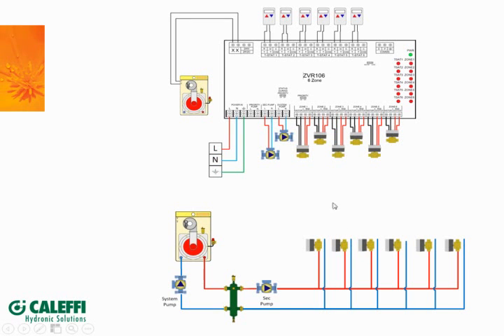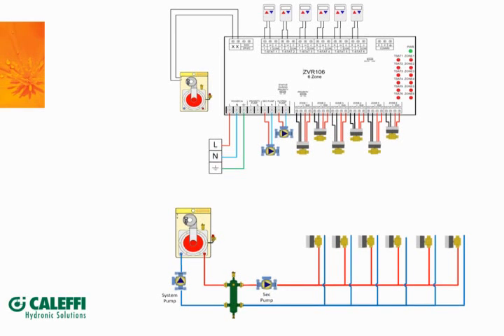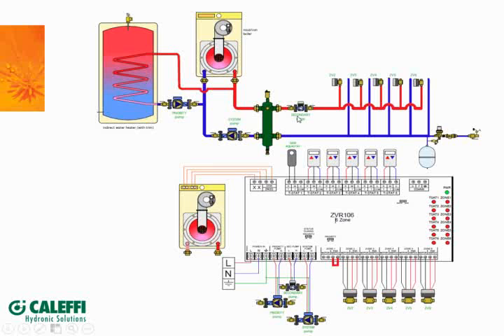booklet color. So here's another, this is another basic one. Kind of touched on this before, but if you had 6 zone valves, a system pump and a secondary pump, the control could control all of those items in that particular system. And getting a little bit fancier here, we have 5 heating zones, our secondary pump, a system pump, and a priority pump. And of course, many boilers can't control that, and that's fine. You can do that if you choose to. Or you could wire them to our control.